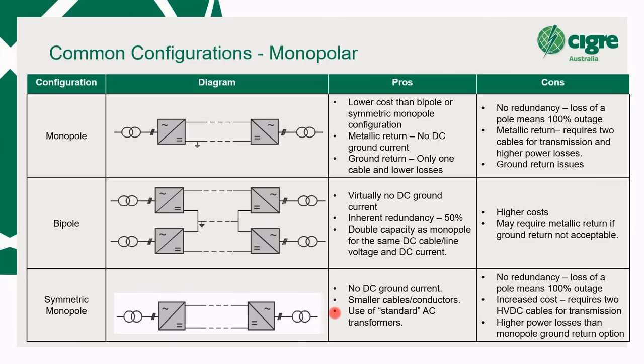And the last one is the symmetric monopole, which DirectLink and MurrayLink are both symmetric monopoles. So a symmetric monopole is basically a positive and a negative pole cable. There's no return. There's no ground current. It doesn't need the shift in polarity of voltage to cause power to change direction, and therefore it's predominantly a VSC type configuration. It has a couple of benefits.